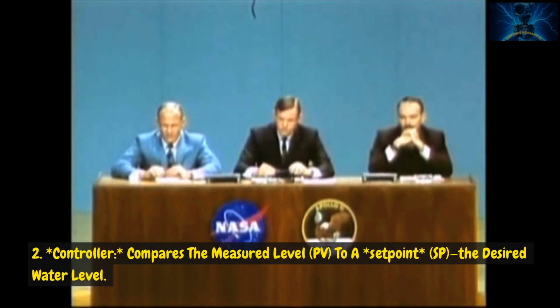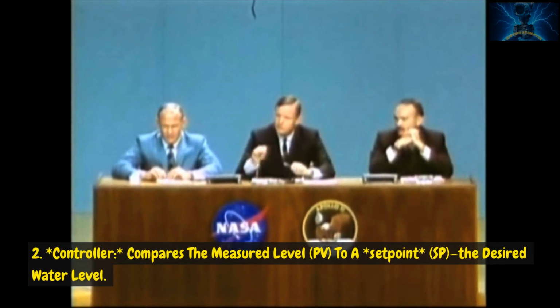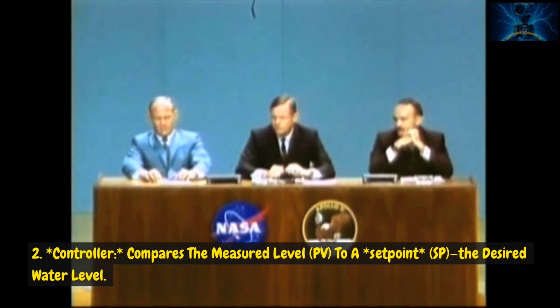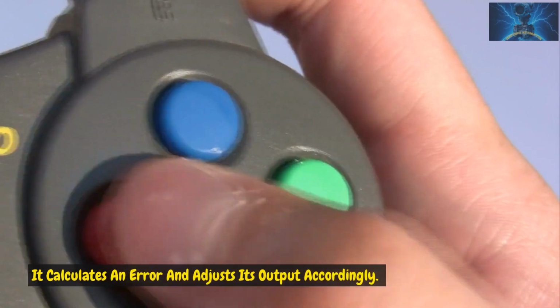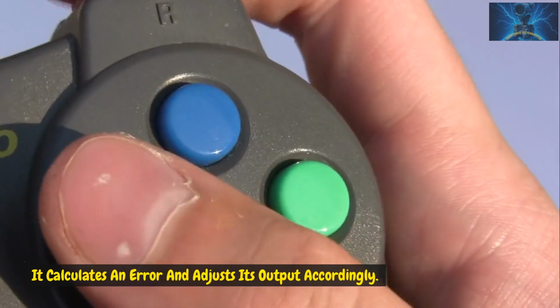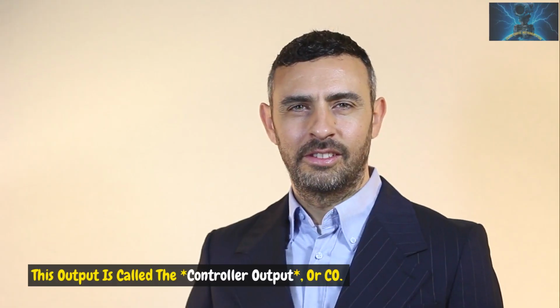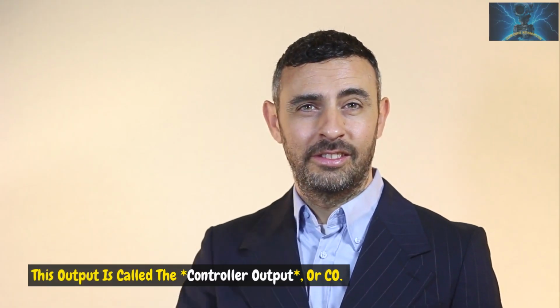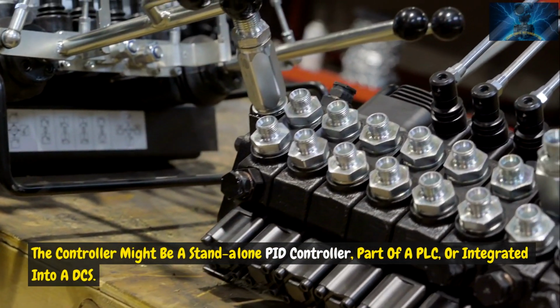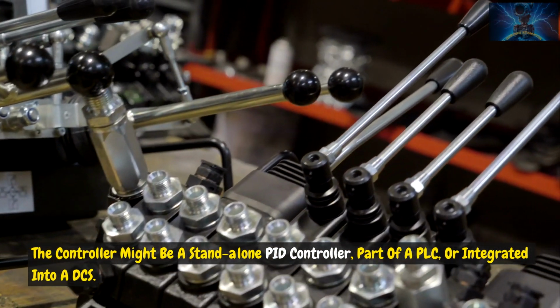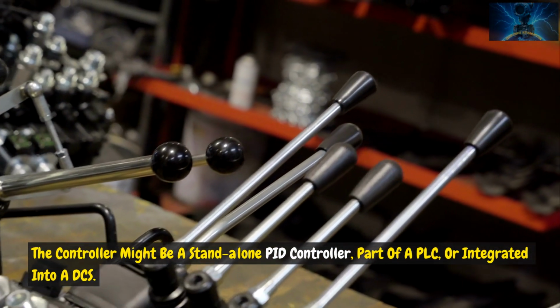2. Controller. Compares the measured level, PV, to a set point, SP, the desired water level. It calculates an error and adjusts its output accordingly. This output is called the controller output, or CO. The controller might be a standalone PID controller, part of a PLC, or integrated into a DCS.